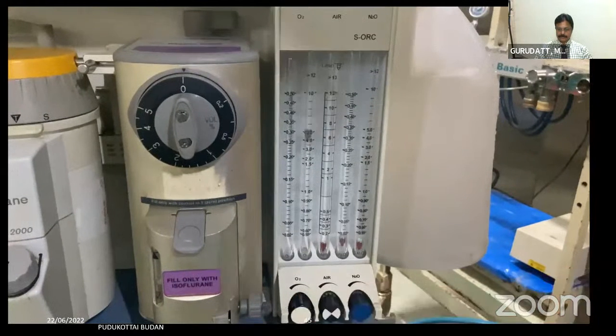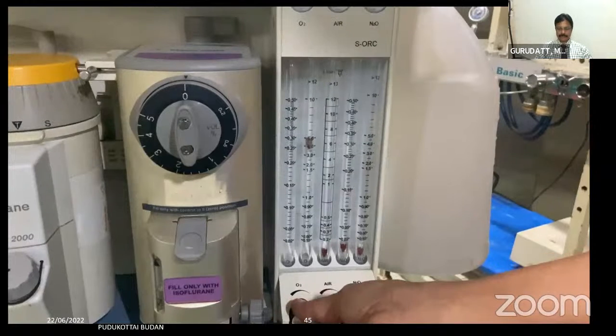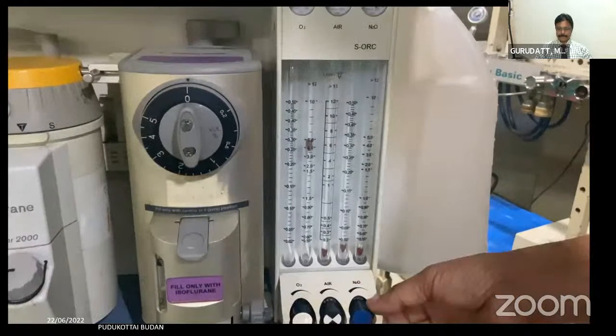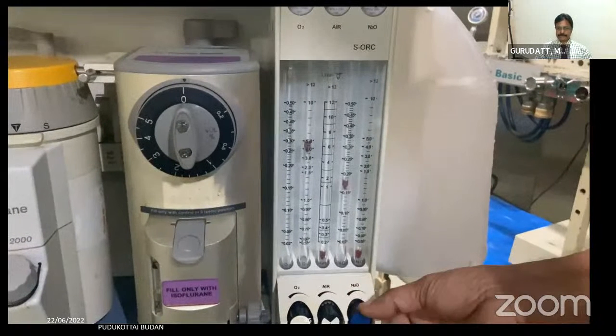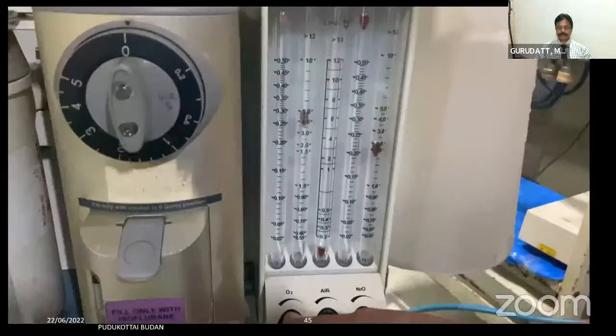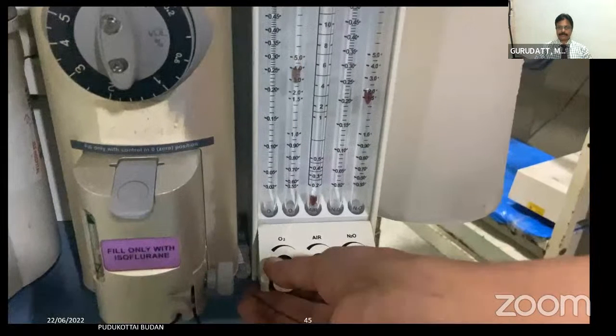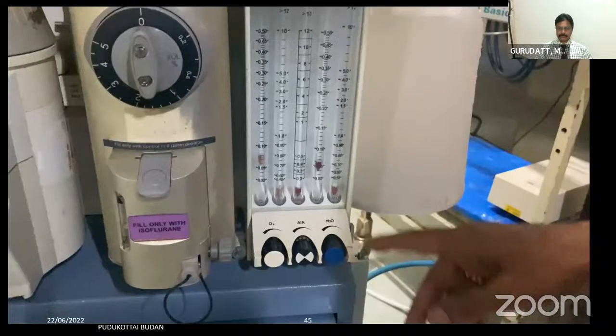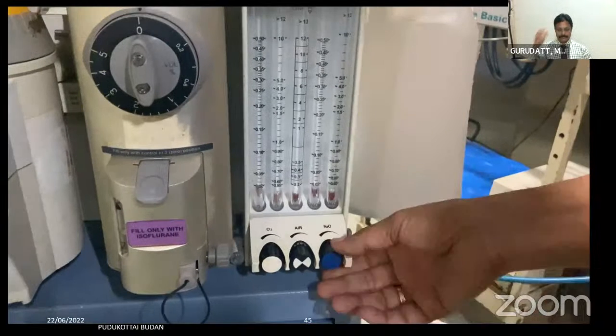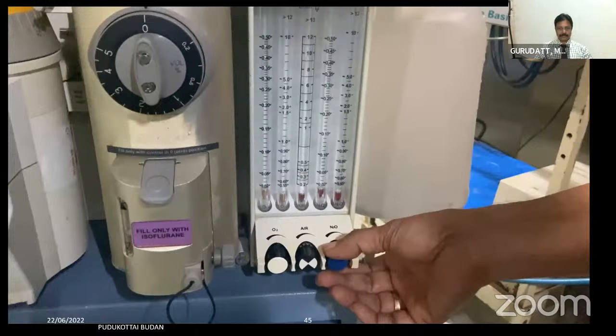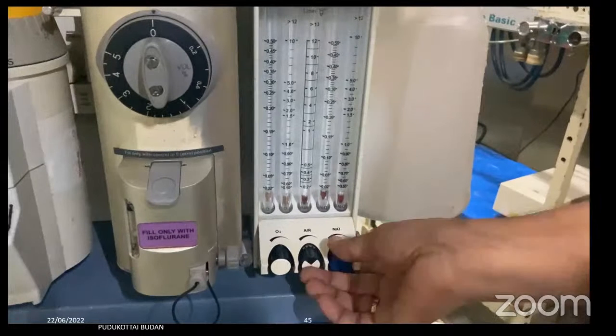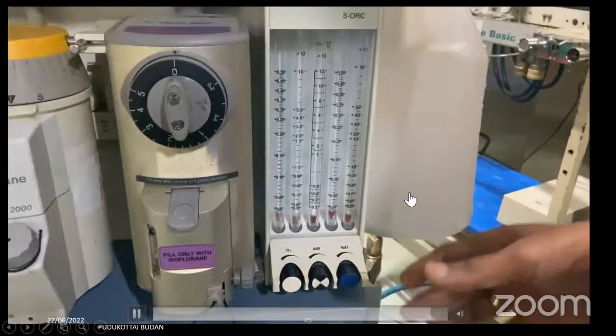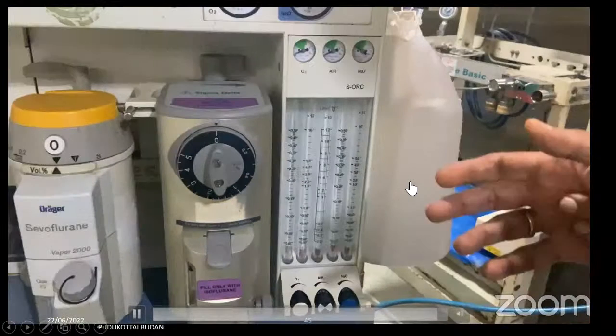Now I have opened oxygen. Now if I open nitrous oxide, I can definitely provide nitrous oxide. Again, if I cut off oxygen, the nitrous oxide automatically also gets cut. And if I try to open only nitrous oxide again, I will not be able to open it. This is what the sensitive oxygen ratio control is.